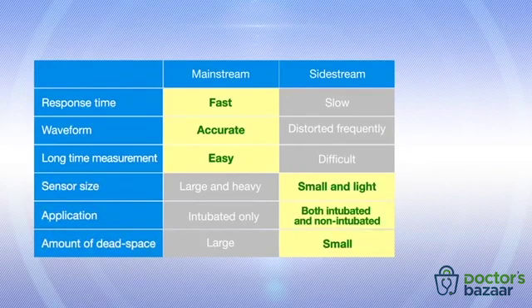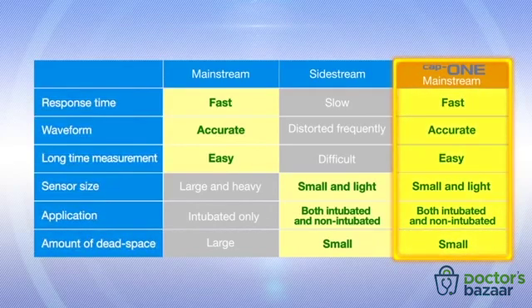Advantages of mainstream sensors are rapid response, less waveform distortion, and few measurement interruptions. But compared to sidestream sensors, mainstream sensors are heavier, limited to intubated patients, and have larger dead space. Now cap-ONE has overcome these disadvantages and maintains all the advantages of the mainstream sensor for optimal capnography.